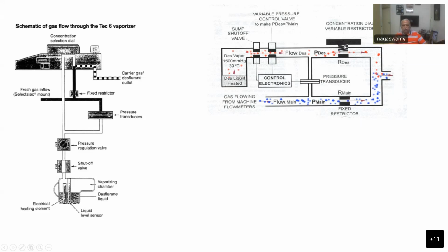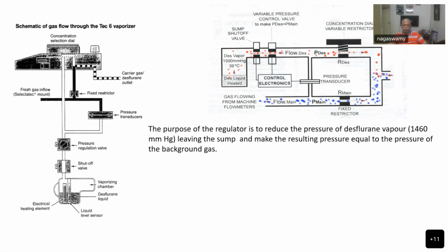And then this dial has a groove which will rotate and open up this gap depending upon the percentage that we set. So both these things will then mix the fresh gas flow and the vapor, and then ultimately deliver that. And the purpose of the regulator is to reduce the pressure of desflurane vapor leaving the sump and make the resulting pressure equal to the pressure of the background gas.